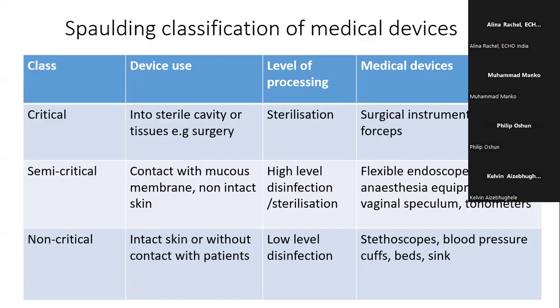If it is semi-critical, semi-critical devices are those that make contact with mucous membrane. They do not enter sterile cavities, but mucous membrane or non-intact skin. For example, endoscopes, anesthesia equipment, vaginal speculum - all these go into mucous membranes, and they are called semi-critical devices. For these, a minimum of high-level disinfection is required; sterilization is also okay, but the minimum should be high-level disinfection. If possible, sterilize. Then the last one is non-critical devices.